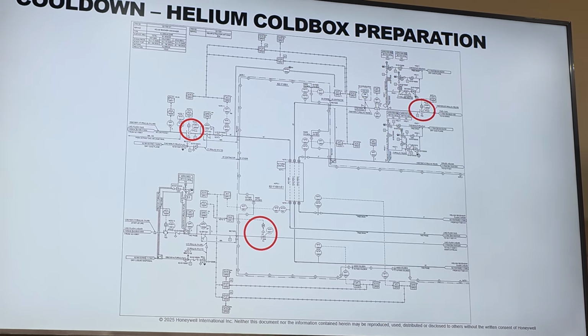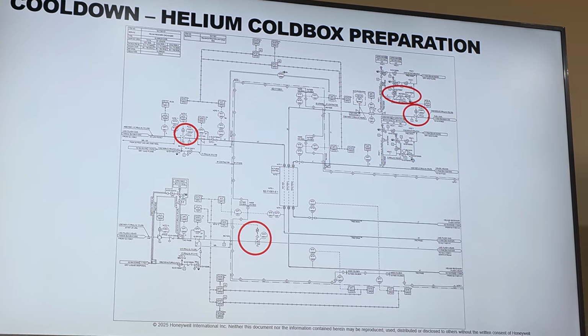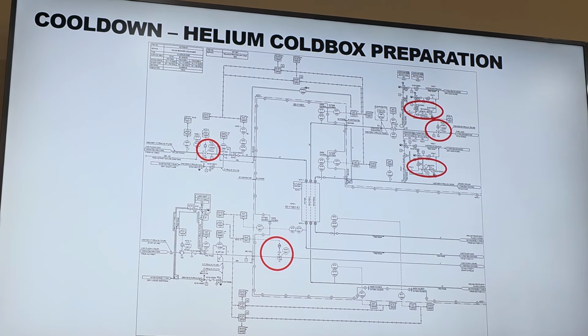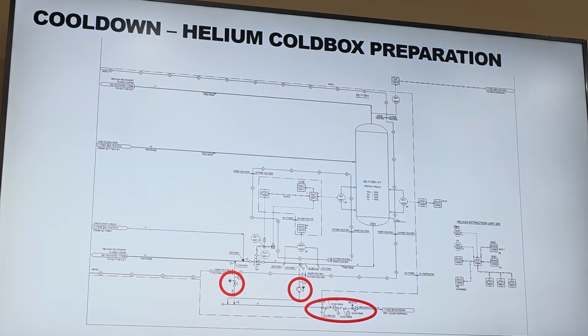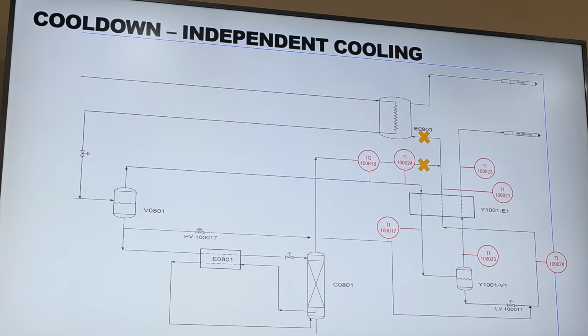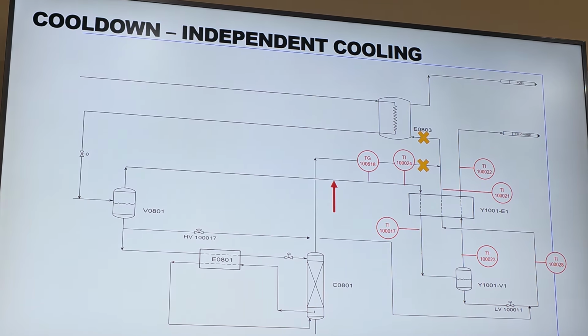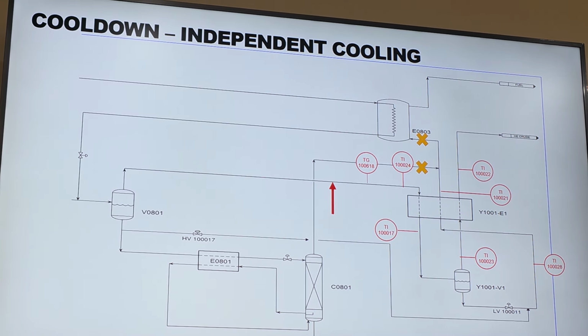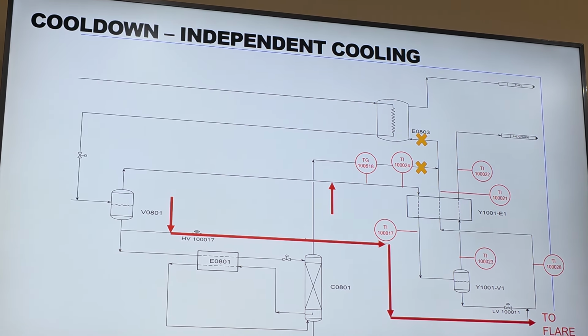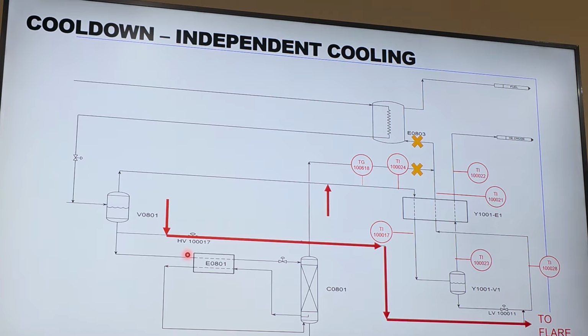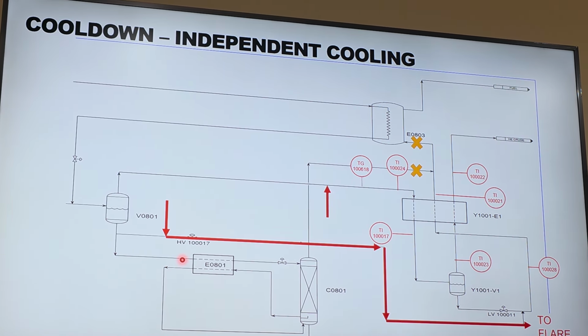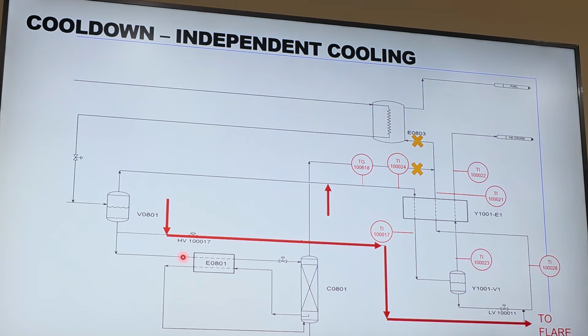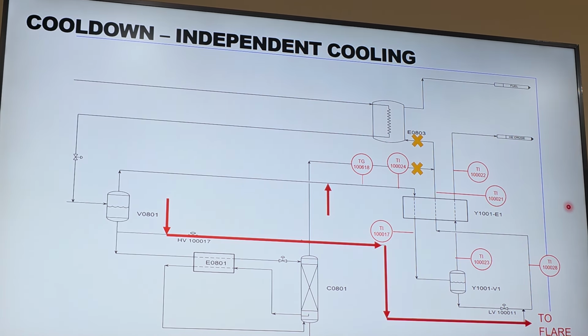So now let's talk about cooling it down. It's basically the same setup as defrost: opening vents, opening up valves to unisolate the equipment, opening up the drains on the flash drum, opening up the level valve. Just like any other cool down, we start with defrost gas flowing, getting a positive flow moving through the system. Then we're going to purge this HV line right here, which you will more than likely use later in the cool down. In the meantime, if you're not going to use it, you do want to flow gas through it to make sure the line has been swept, okay?